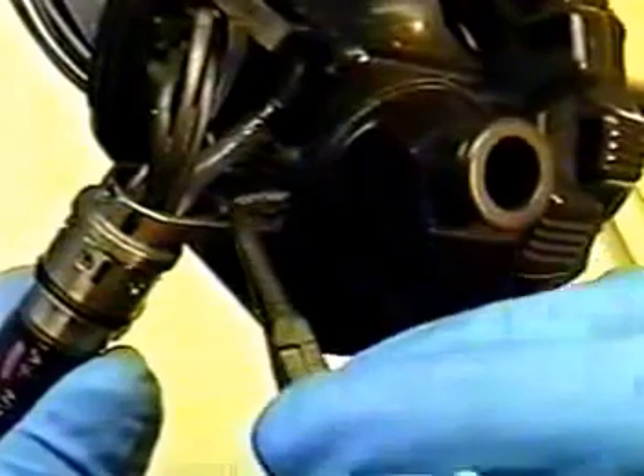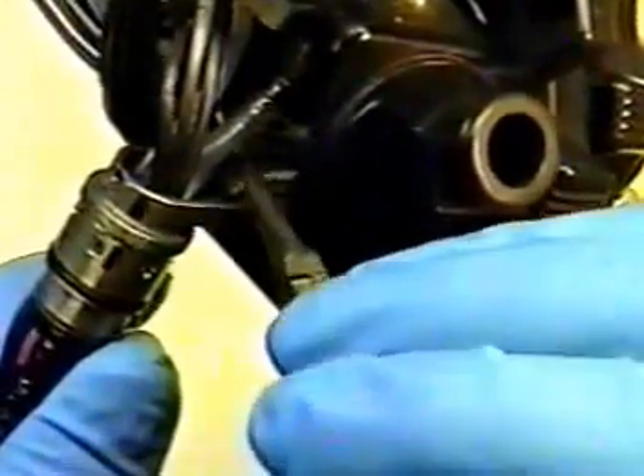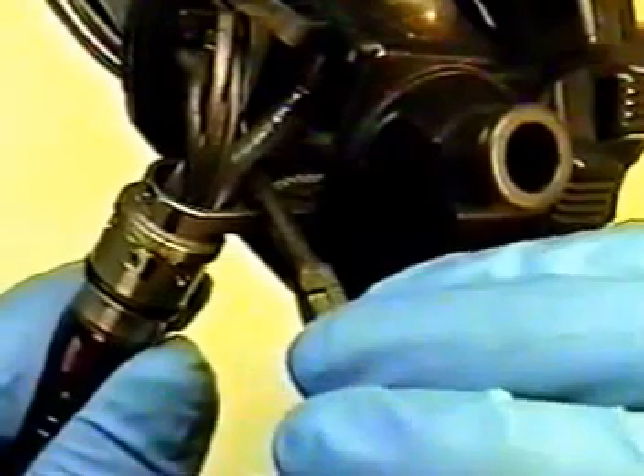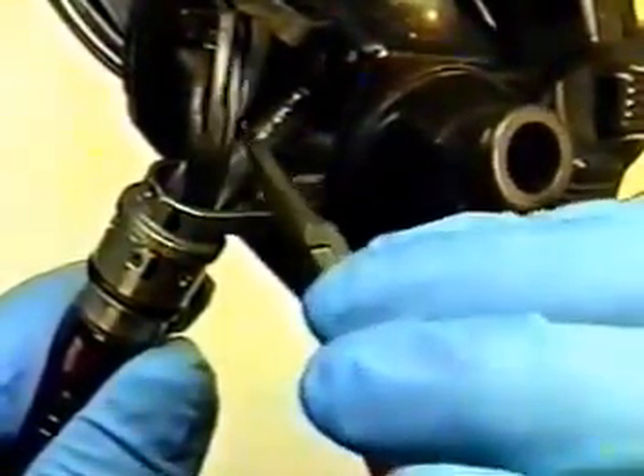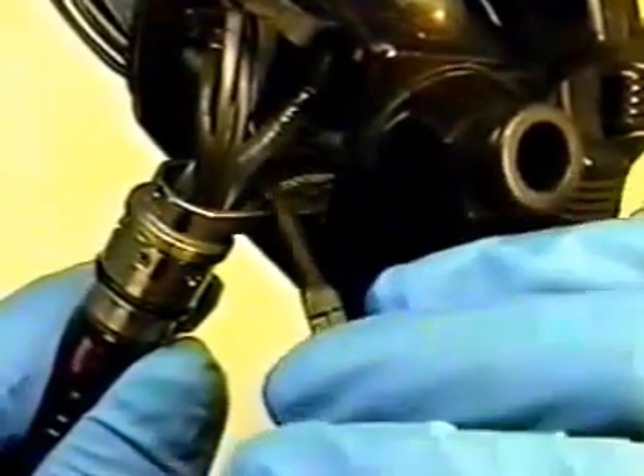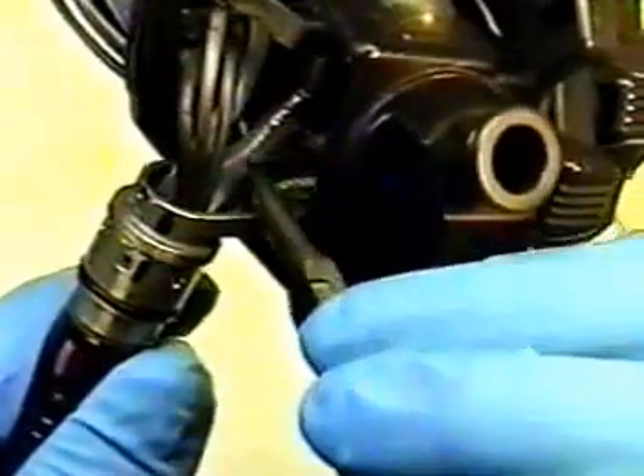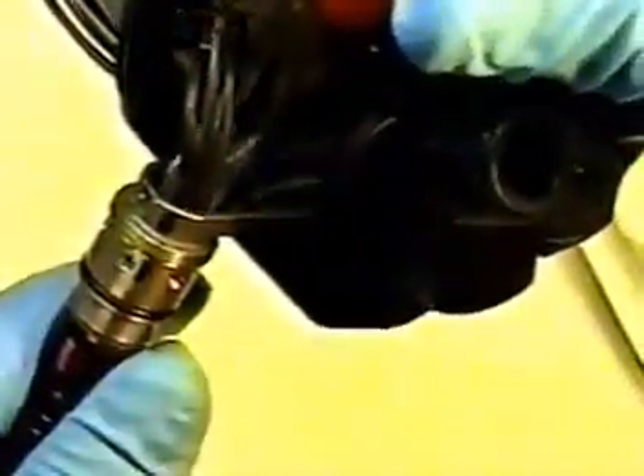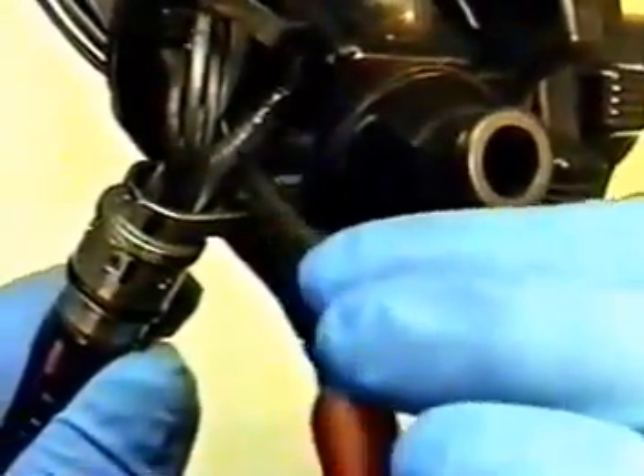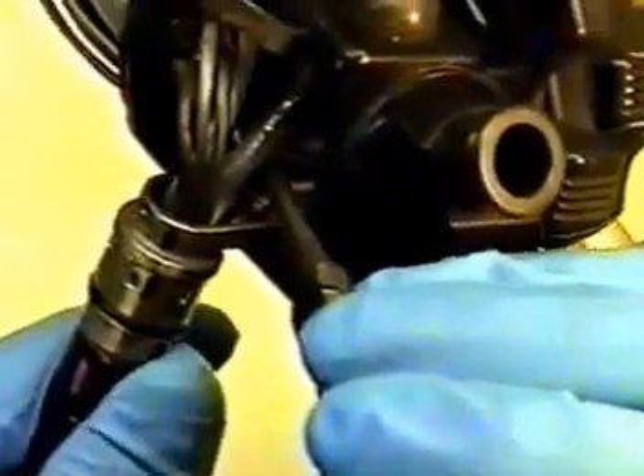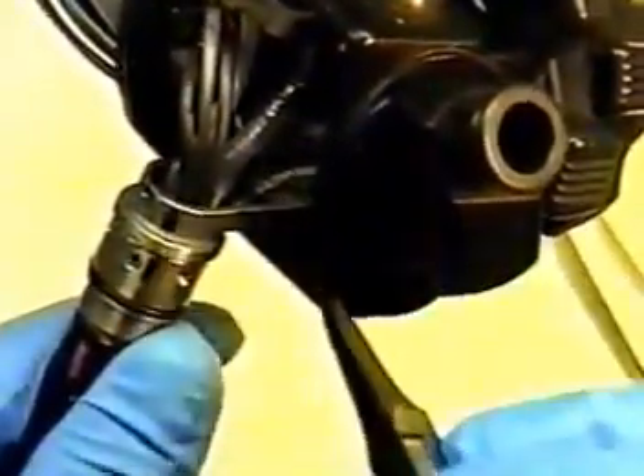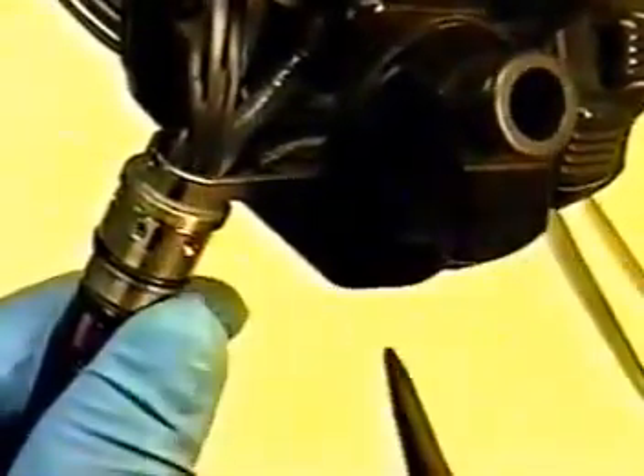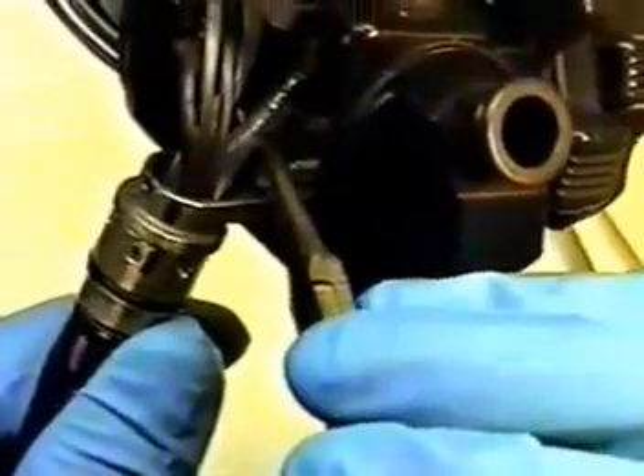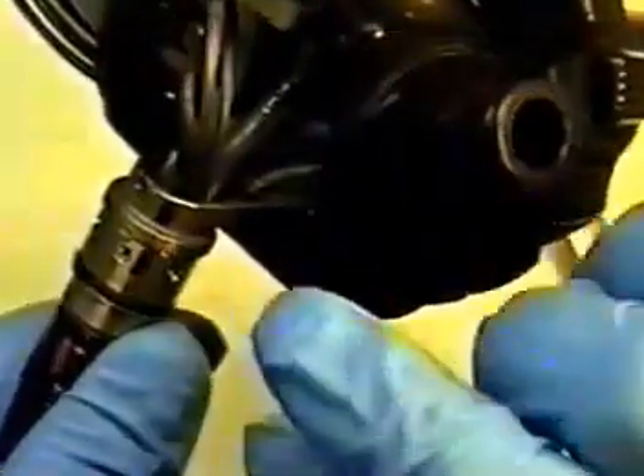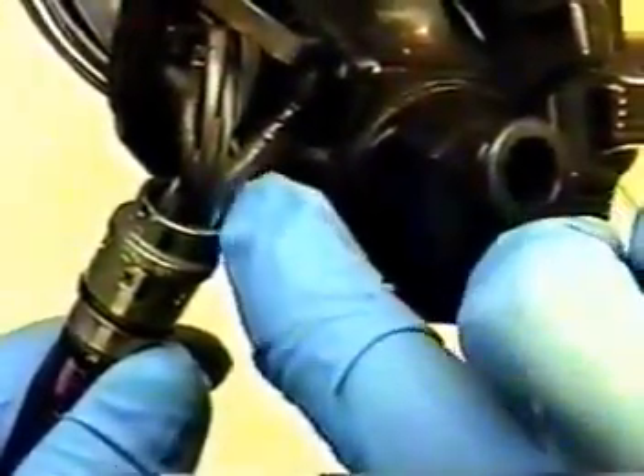Be careful not to kink this suction channel, because that will not allow the forceps cleaning brush to pass through and will restrict suction during procedure. Again, be extremely careful not to crush any of the other tubings and light bundles or CCD wiring assembly. If you do kink this tubing, use your pliers and remove the kink from the channel. It is very difficult to get in here and will take a little practice to get this tube up onto the port. If you're using a 5-minute epoxy, of course it will need to be done very quickly, but be very careful. It is advisable to use standard bending rubber epoxy, letting it get tacky first for an hour and then letting it dry.